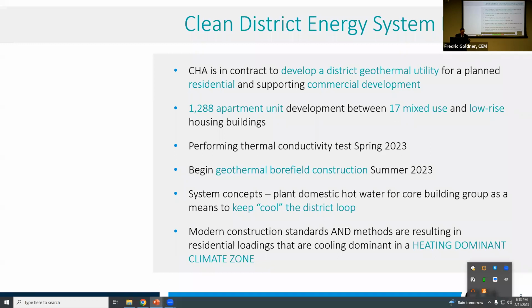The concept is that I have an unbalanced load. Those apartments have a greater cooling load than heating load, so I'm seeing about a third of a degree uptick per year of load imbalance. As Caitlin mentioned, these utilities have to promise an ambient loop within certain temperature ranges. One way I'll keep my loop cool is by doing geothermal hot water, which wrenches the heat off this loop and turns that into potable water or shower water for that core group of buildings.